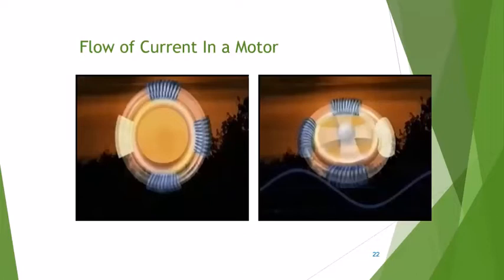So again, what we're doing with the first machines is we're taking that rotating field that you have in an induction machine, which is here, and it's inducing it into the rotor from the sine wave. In order to change that speed, we're changing this sine wave, we're building new ones. And that way we're able to control the speed of the rotor. Otherwise, before, we had to use the DC machines that were used in the past.